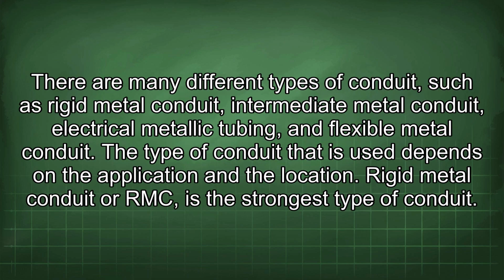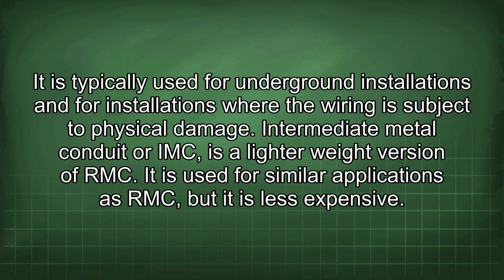There are many different types of conduit, such as rigid metal conduit, intermediate metal conduit, electrical metallic tubing, and flexible metal conduit. The type of conduit that is used depends on the application and the location. Rigid metal conduit, or RMC, is the strongest type of conduit. It is typically used for underground installations and for installations where the wiring is subject to physical damage. Intermediate metal conduit, or IMC, is a lighter weight version of RMC. It is used for similar applications as RMC, but it is less expensive.